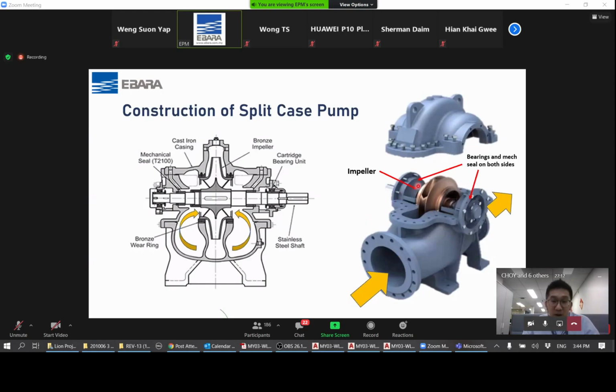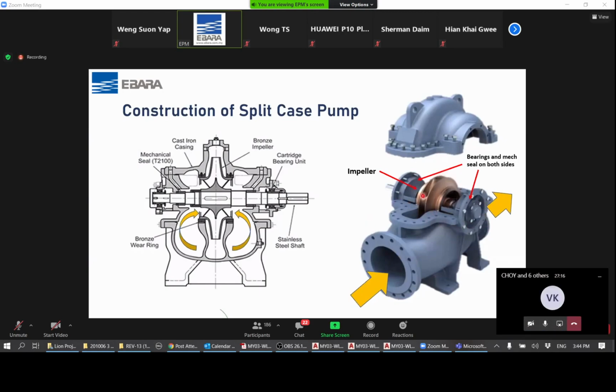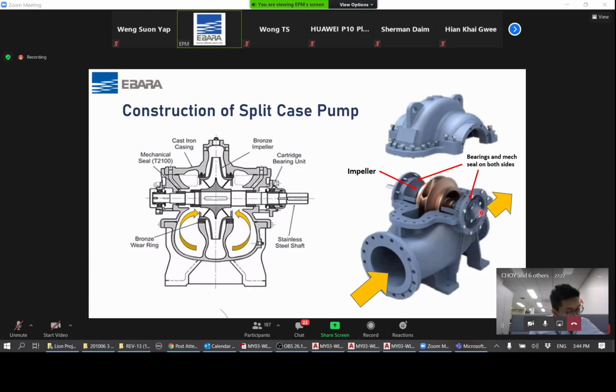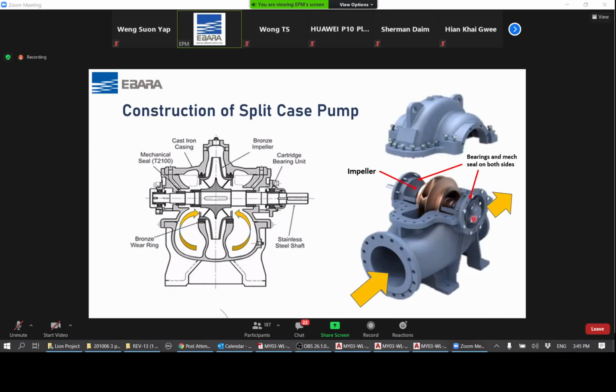And if you see also from here, one of the very good construction is that the shaft is supported by bearings on both sides of the pump. So it is a very balanced construction, and also mechanical seals on both sides of the pump. So that's why split case pumps tend to have much higher efficiency compared to many other type of pumps.